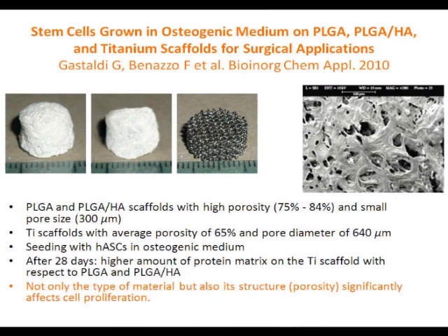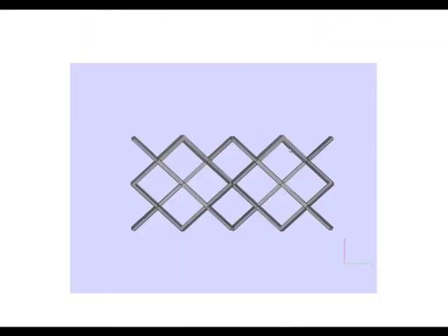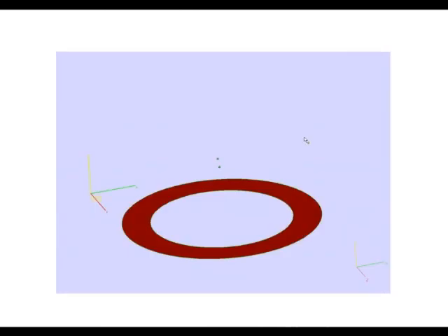Trabecular titanium is a metal, it's titanium, but the porosity is controlled, and it is produced with electron beam melting of titanium powder. This is how a hip cap, the cap for the hip replacement, is built. The factory is here in Sicily, but it's time consuming because in one night procedure we can have 20 caps like that. And if you increase the pore size, and you can do that only by acting on the software, you increase the elasticity. Of course, it's a metal.